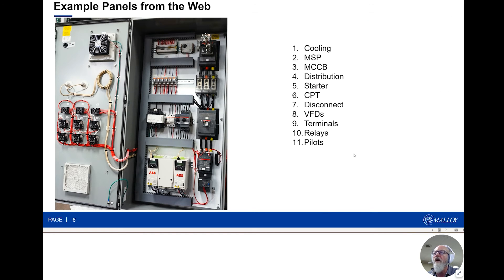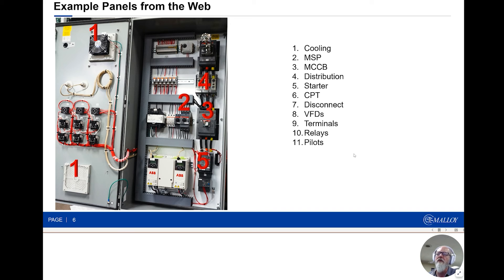The last example is a bit different. We're looking at cooling on the door — it includes the door, top and bottom. The motor starter protectors are again used here to protect the drives. This design has two drives and one starter, so there are three sets of pilot lights. You have a molded-case circuit breaker, a distribution block, a contactor, and a starter — presumably because they needed two VFDs to control speed and a third motor that didn't require variable speed or soft starting. Then there's a control power transformer, an isolating disconnect, the drives, terminals, relays, and of course the pilot lights.